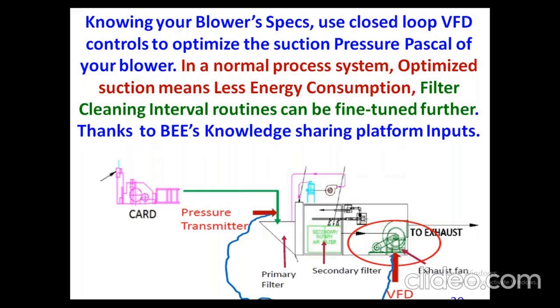The first slide which I was telling you, the 25% energy savings done by Soumya Spinners, Coimbatore, is mainly due to the variable torque loads, and this waste collection blower is a critical area where the percentage of energy savings is very high. You can concentrate on all the blowers in the textile mills and the axial flow fans.